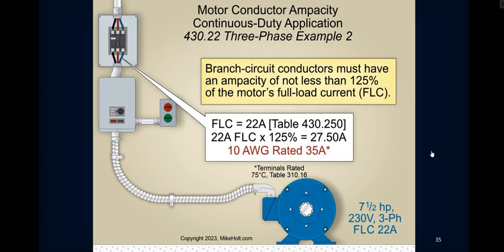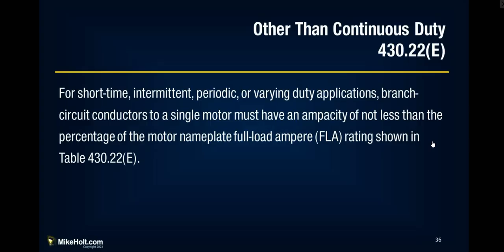Well, if you look at table 310.16, depending on what column you are operating out of will depend on that basic ampacity. For instance, a great thing to make a note of for testing in the future is NM cable comes from the 60 degrees Celsius column. When you are sizing conductors and you're looking at branch circuits in the residential sector, such as a single-family dwelling, apartment building, or multifamily duplex, you would be in the 60 degrees Celsius column because you're more than likely using NM cable. So sizing conductors at that point would be there. Otherwise, from a testing standpoint, you would see that given in the question in order to make sure you were in the right spot.